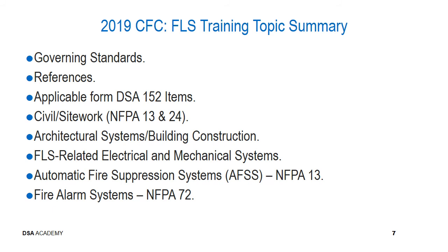So let's go over what we've talked about today. We reviewed governing standards, references, applicable DSA 152 items, the interrelationship between NFPA 13 and NFPA 24 as related to civil and site work. We've gone through the architectural systems and building construction for those critical elements to fire and life safety, such as fire stop systems, fire-rated construction, and opening protection. We've discussed the fire and life safety related electrical and mechanical system elements, automatic fire suppression system features of NFPA 13, and the inspection and testing verification for fire alarm systems in NFPA 72.